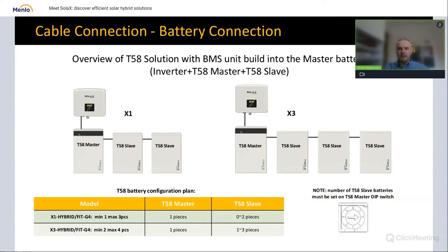That is for installers. And for those who are selling, as a salesperson you must know that when selling a 3-phase inverter, you have to sell a minimum of 2 batteries with it. 1 battery won't do - 1 battery is good for single phase. For 3-phase, it has to be a minimum of 2 batteries and a maximum of 4. So for those preparing offers for customers or doing projects, you have to remember this minimum and maximum number of batteries.